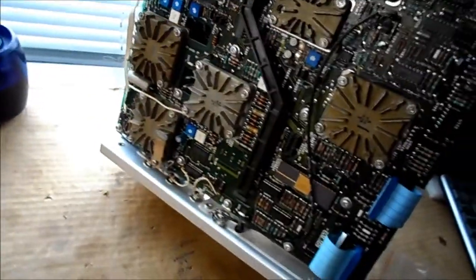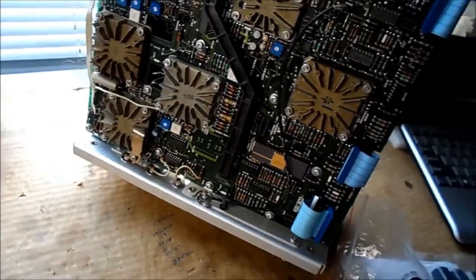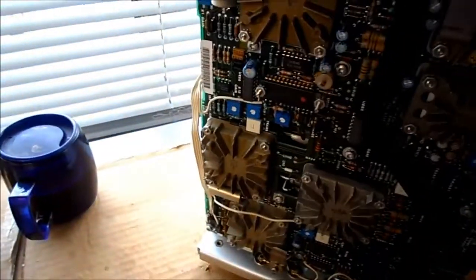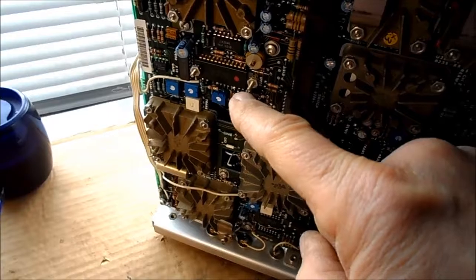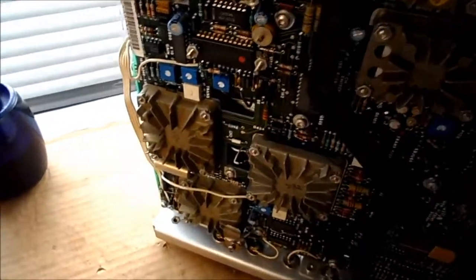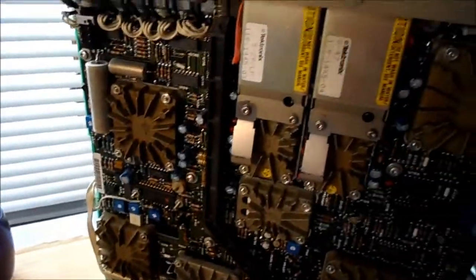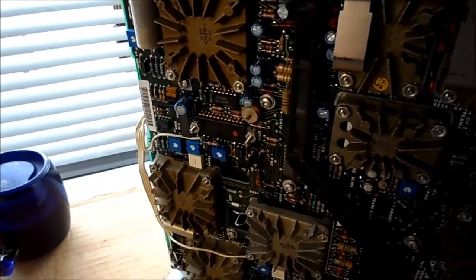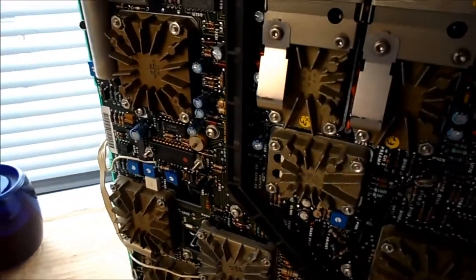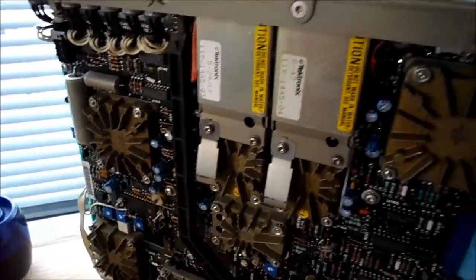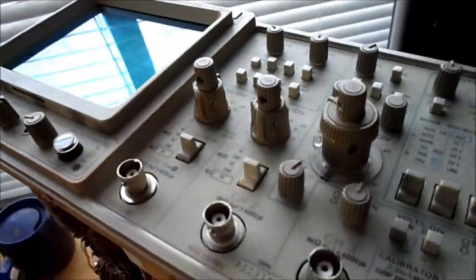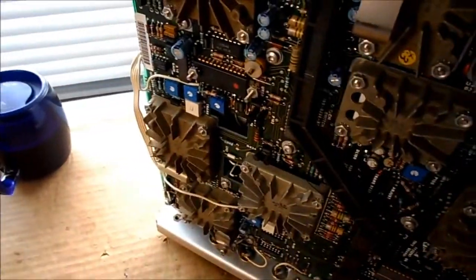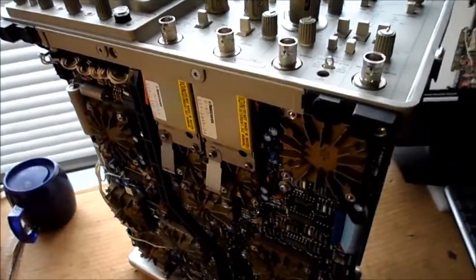I don't know if it isn't broken, don't fix it, they say. But where is that chip on mine? It's this one right here with the red dot on it. So I'm not sure if I'm going to put a heat sink on that or not. I probably, I would guess it probably wouldn't hurt to put some aluminum radiation on that, put a radiator on it so it can not have that problem. Because that's the Achilles heel of this particular line of scopes of 2465, is that chip's prone to fail due to overheating.